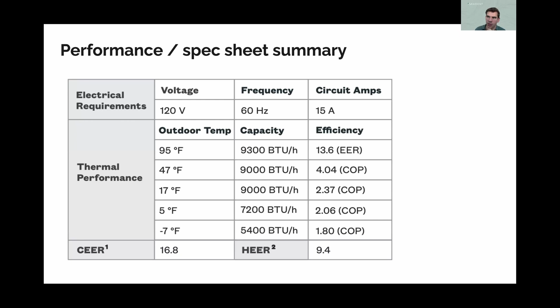Here you can see the capacity this spec sheet is rated at is 9,000 BTU per hour, and you maintain 100% of that capacity at 17°F. You're also at almost 2.4 COP at that lower temperature, and it's that lower COP that really helps ensure you can work with the existing building electrical infrastructure as much as possible.